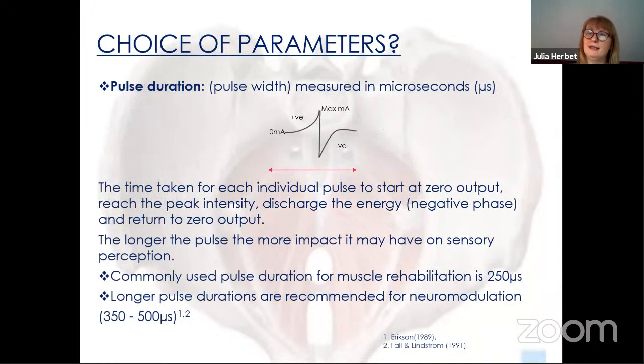The next parameter that is often preset on the machine but can be changed, and they are different across different machines, is the pulse duration. This is sometimes slightly incorrectly referred to as pulse width, because it's a measurement of time. So it's a duration, it's a measurement in microseconds. And it's basically the time that it takes for an individual pulse to start at no output, to reach what we've set on the machine as the maximum milliamp intensity, and to go back to its 0 output at the end of the pulse. So you can see the positive phase, the negative phase gets back to 0 again, and it's that length of time.